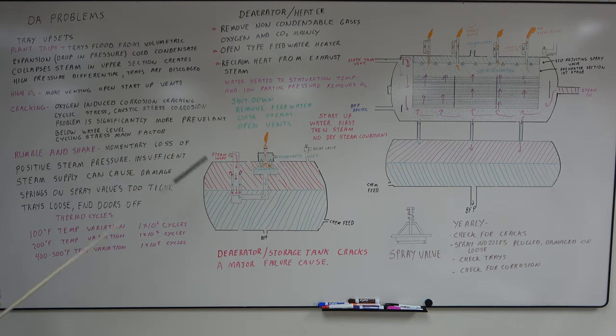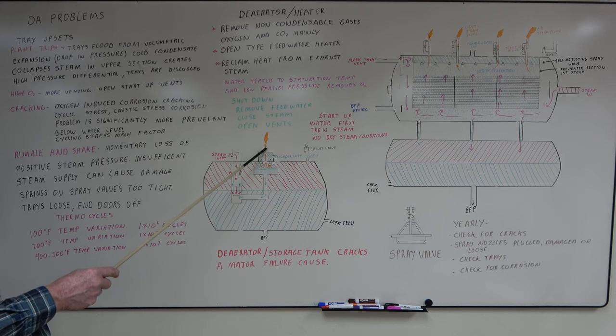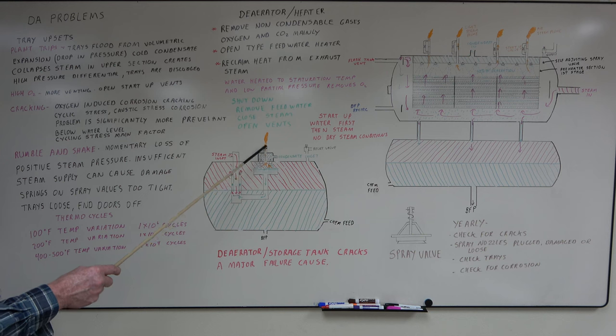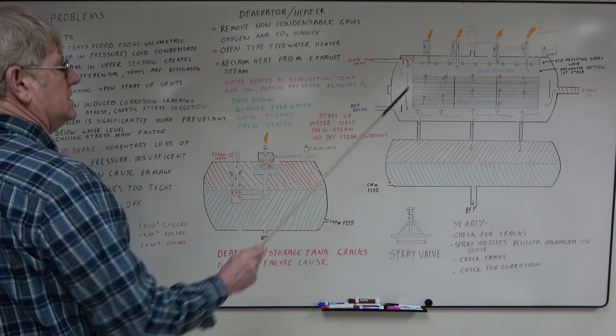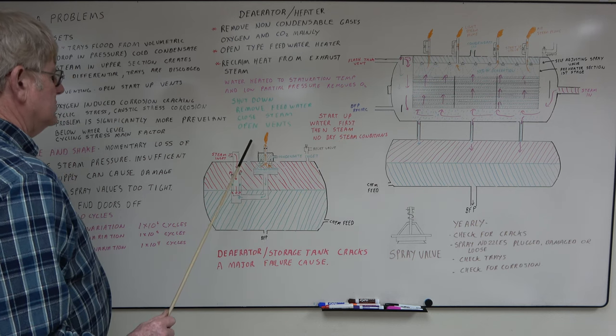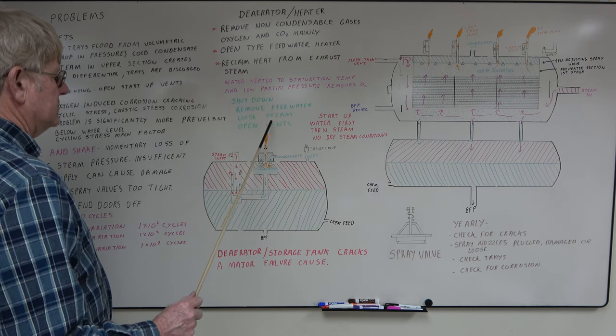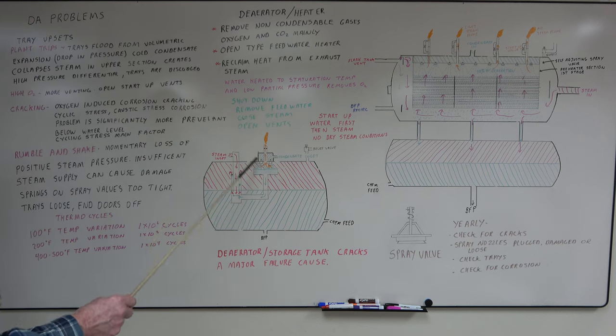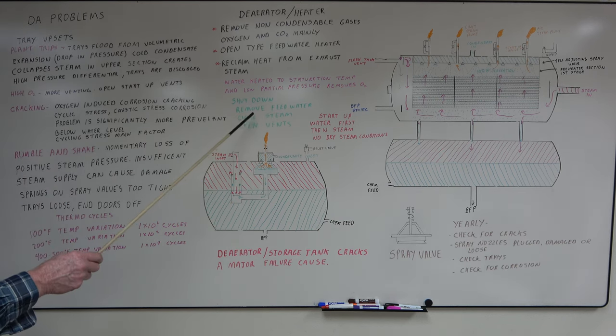High O2. You have high O2 on a deaerator, it's probably not venting correctly. You need to check the steam inlet. Usually they have an orifice on your line coming out of the deaerator. There's also valves like this. It has starter valves. You may have to vent more, but usually the orifice is big enough so you have just this light plume of steam coming out. You don't want it blowing out and you don't want no steam at all.